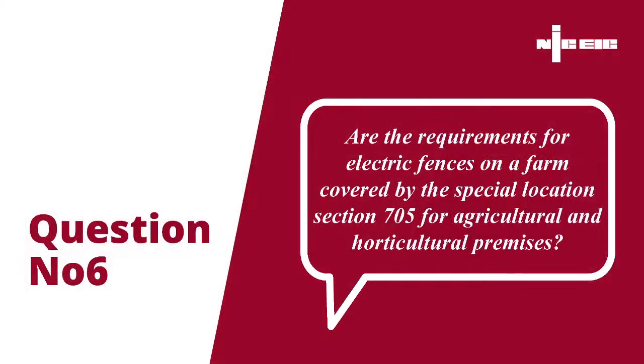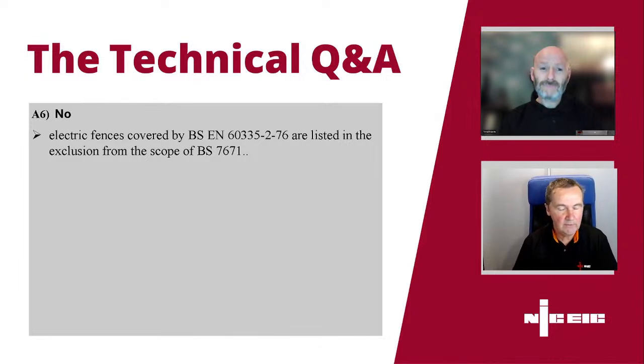We'll finish off with the last one, nice and clean again. We had a request for information regarding an agricultural installation and electric fences - are the requirements for electric fences on a farm covered by the special location section 705 for agricultural and horticultural premises? Again, nice and simple, no. You won't find that specifically stated in section 705, but it's clearly stated that electric fences are covered by a different standard outside of 7671, listed in the exclusions right at the front of the book. That's where it tells us that animal-associated electric fences aren't anything to do with 7671 - 110.2 covers the exclusions, I believe.